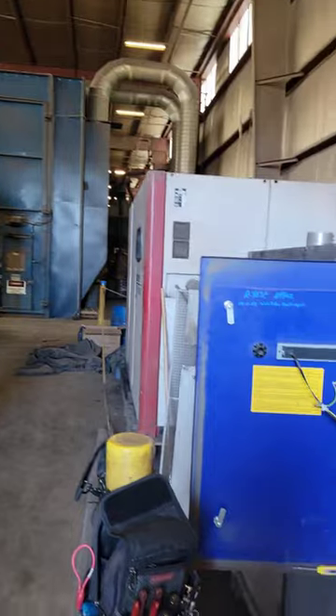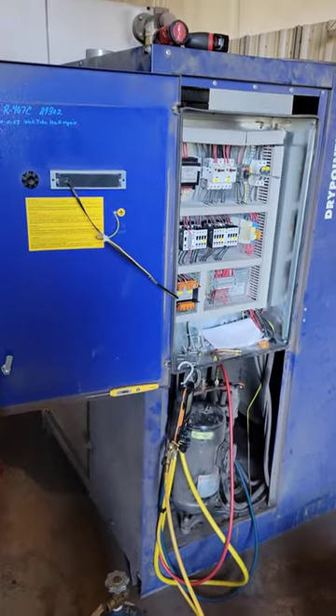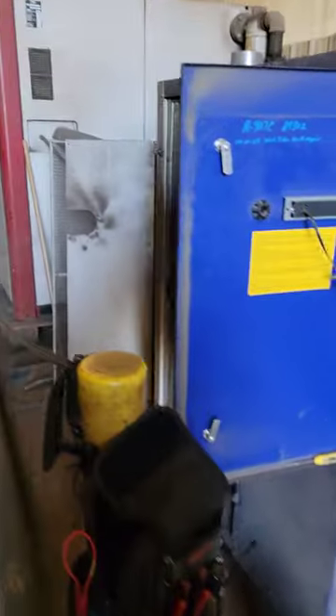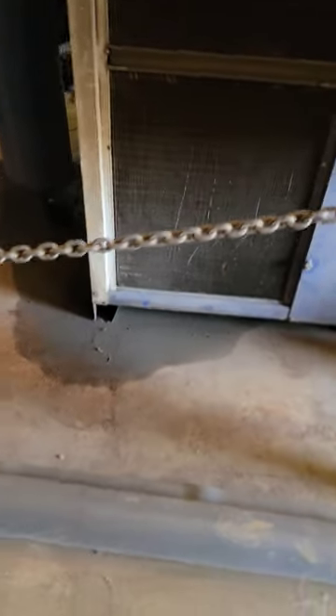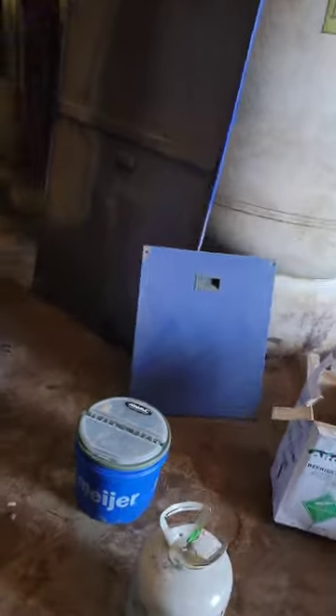We're working on an air dryer that had issues. The air compressor had some oil leakage, and it ended up coming down to a refrigerant leak. We're moving over to the side to show you where the leak ended up being.